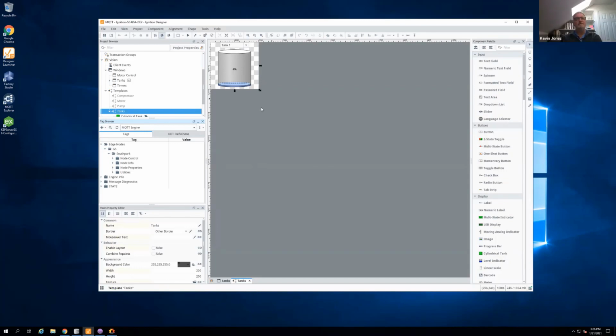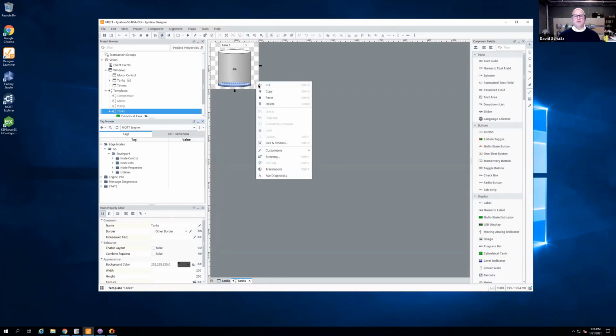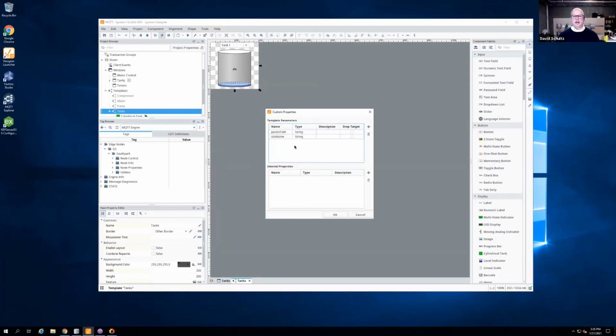Cool. So getting into the project, I've started in Ignition by doing a template. I just have a single tank that I've drawn here. If you go in and look at some of the custom properties, I'm using a concept known as the parent path. That allows me, anywhere that I utilize this topic namespace in trying to draw out a tank, to use the parent path.